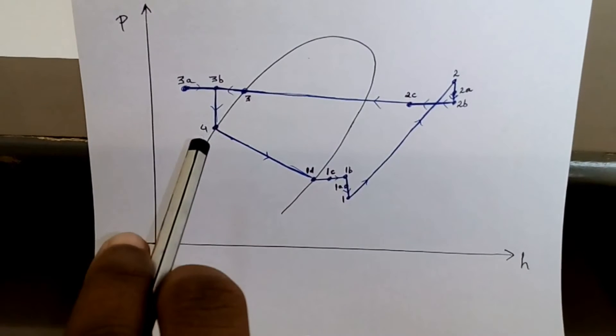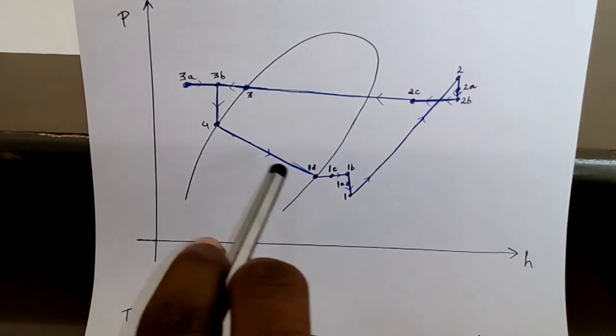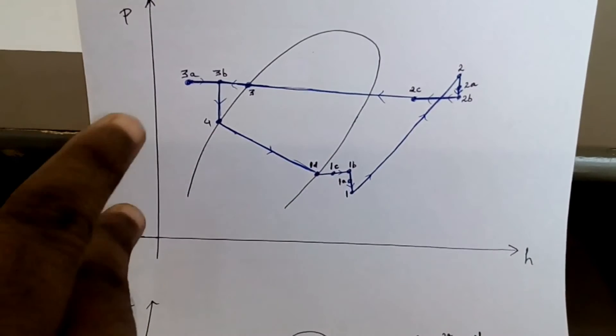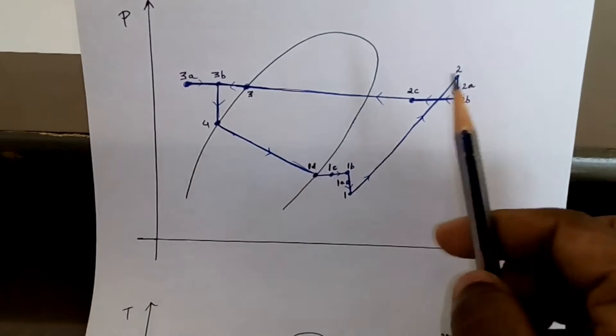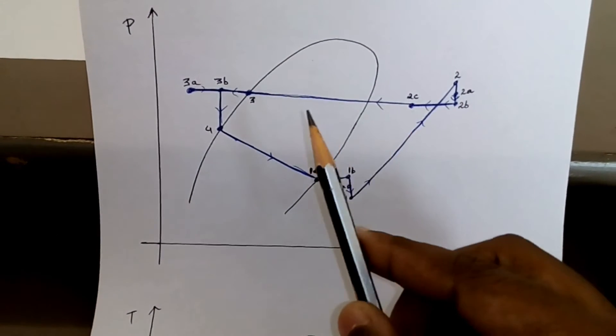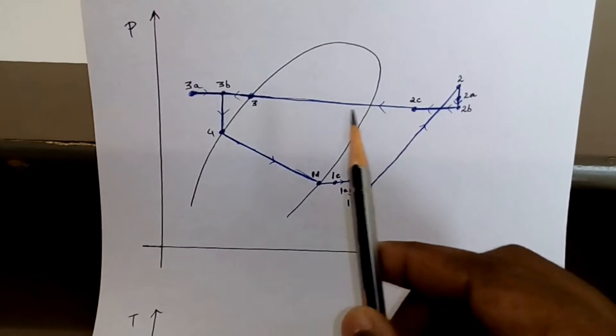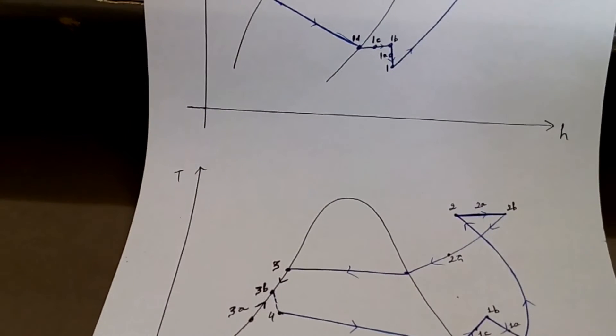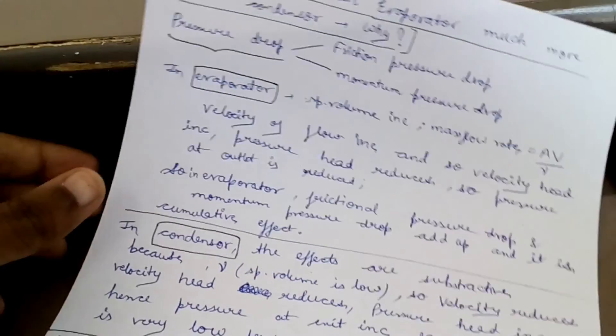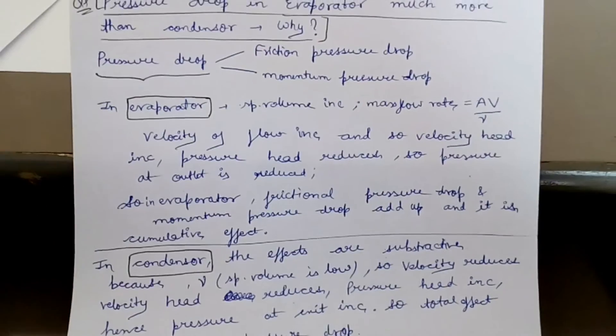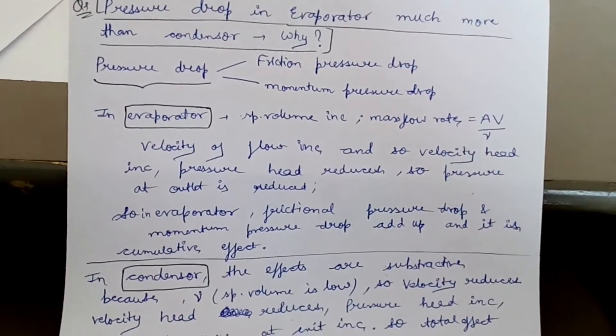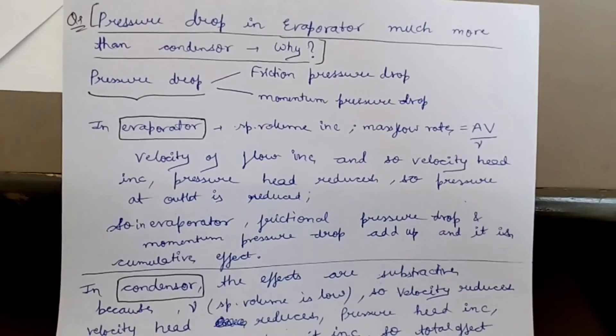The first key point: there is a much larger pressure drop in the evaporator from 4 to 1b compared to the condenser, where the pressure drop from 2c to 3b is much smaller. The question is: why does this happen?